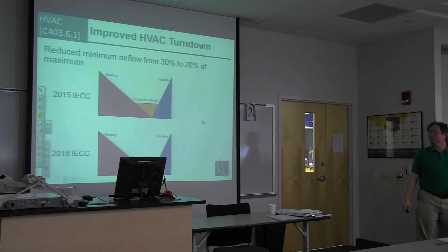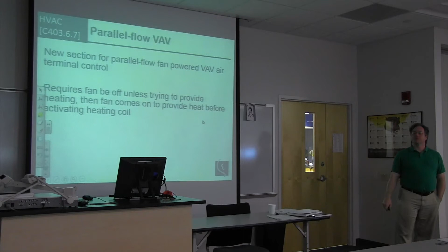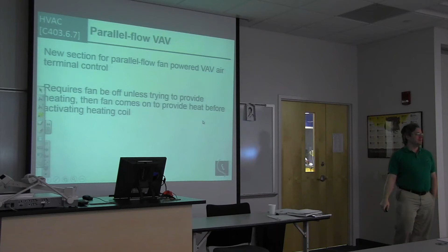So this can also play a role as far as sizing of equipment, because if people oversize their equipment, you're going to have a problem reaching these turn down levels. Parallel flow VAVs, so if you've got fan powered VAV boxes, there's additional control requirements. How many of you run into much of this for any of your designs? I was figuring there weren't too many that this runs into.